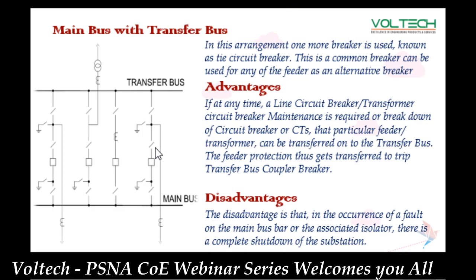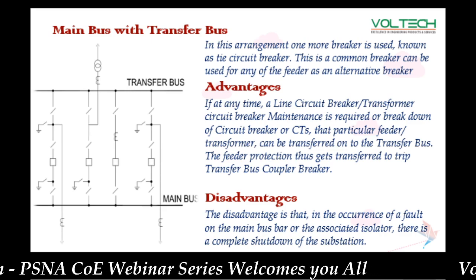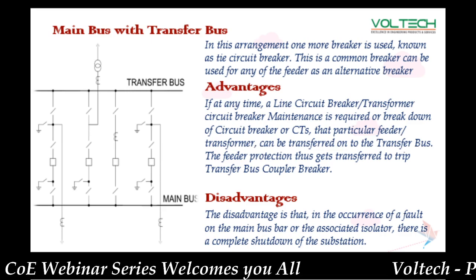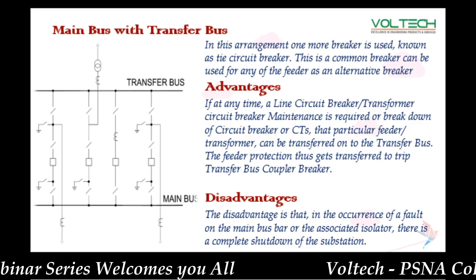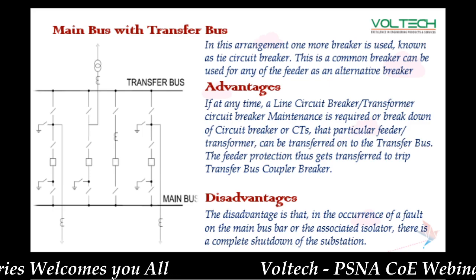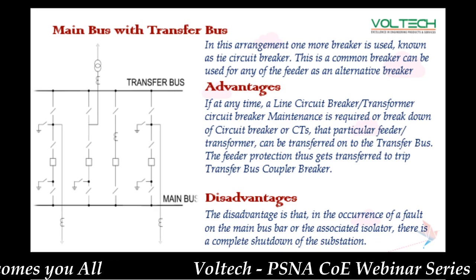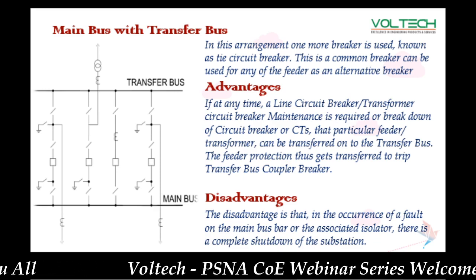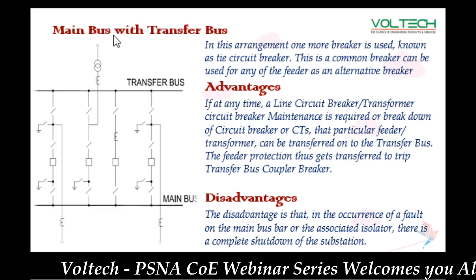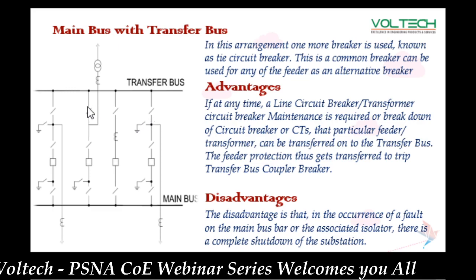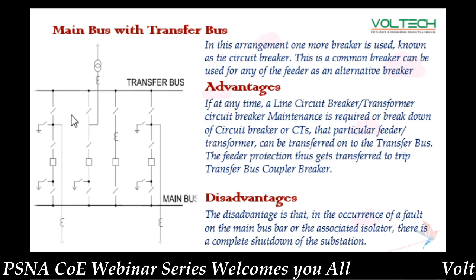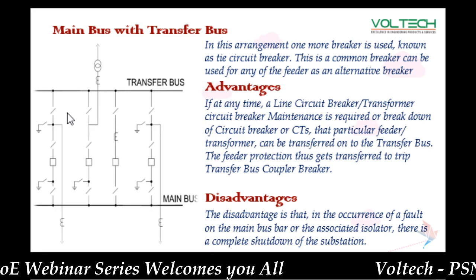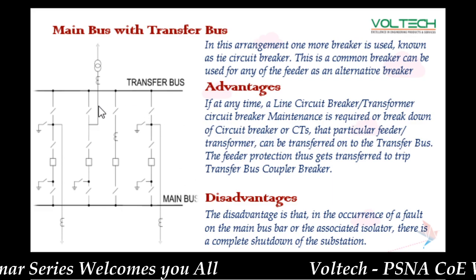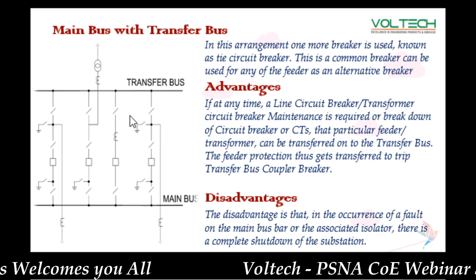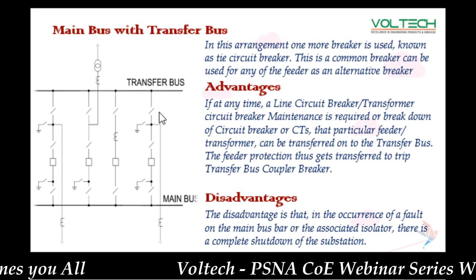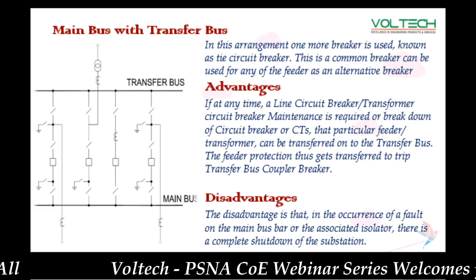Then we can turn both power flows. The advantage is simple: it saves maintenance time. During the maintenance time there is no interruption of power. But the disadvantage is during fault clearance there is a problem in the transfer bus. The fault will not be cleared automatically. That means fault clearance is not possible, because on the transfer bus there is no breaker. It has isolators. All the transfer bus is connected with isolators. If any fault occurs, there is no breaker to interrupt or isolate the power. This is the main disadvantage in the transfer bus scheme.